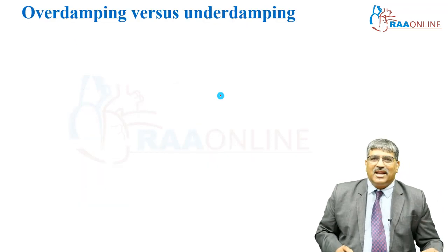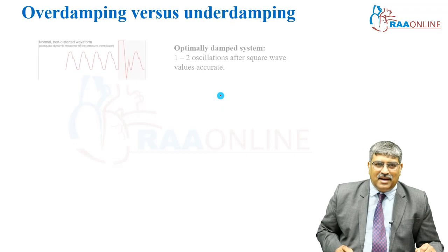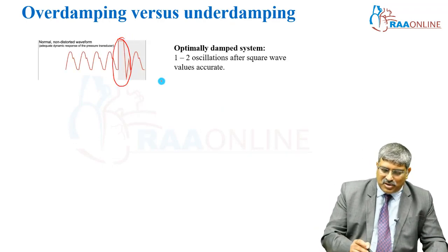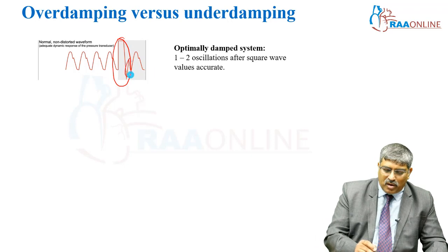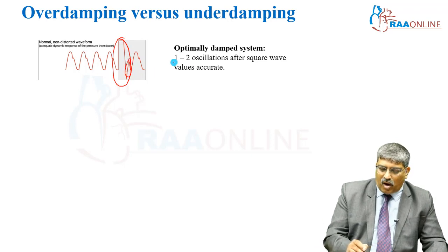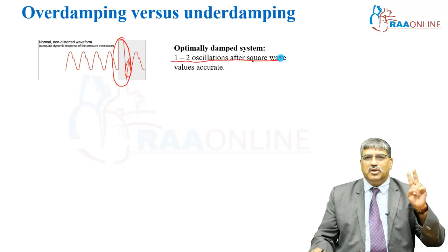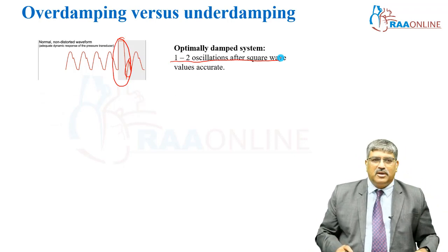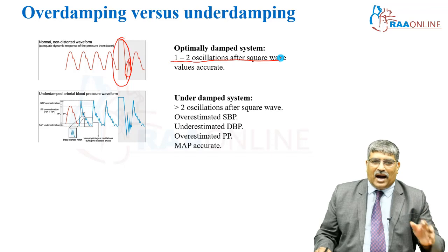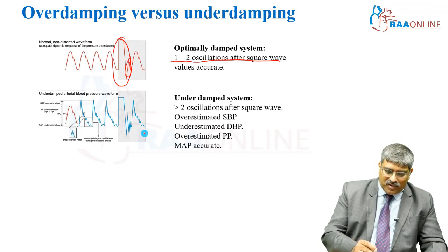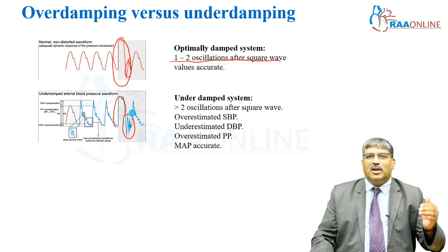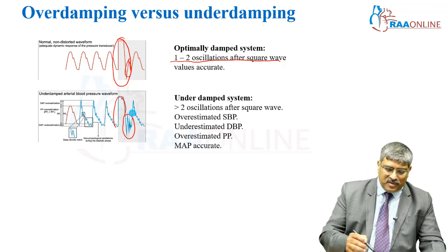Coming to over-damping and under-damping. Normally when you do a square wave test, you have 1 to 2 oscillations — this is the optimally damped system. In an under-damped system, when you do a square wave test, you will have more than 2 oscillations.